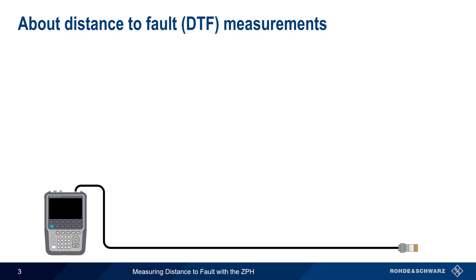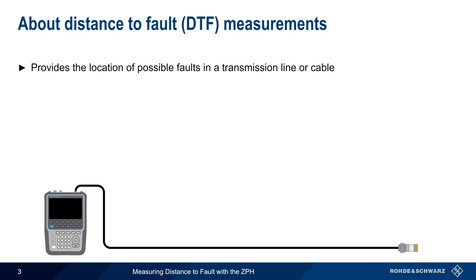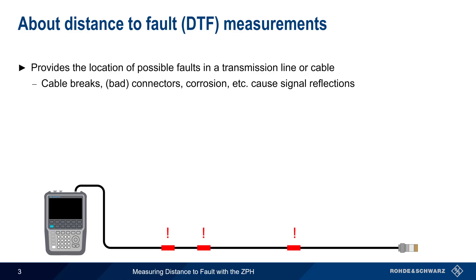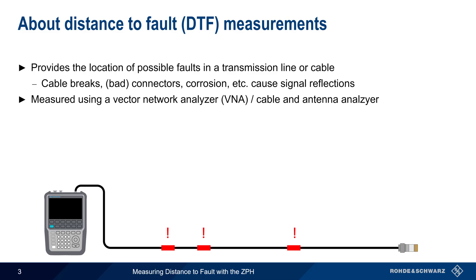Let's start with a brief overview of Distance to Fault. Distance to Fault measurements provide the location of possible faults in a transmission line or cable. These can be due to cable breaks, bad connectors, corrosion, animal chews, etc. Signal reflections will occur wherever these faults are located, and we can use a Vector Network Analyzer or Cable and Antenna Analyzer to make distance to fault measurements.